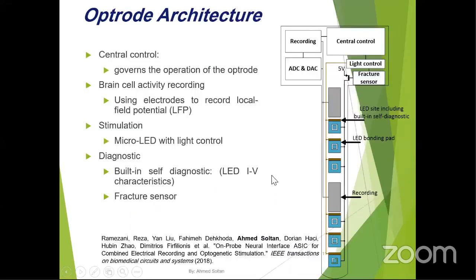Okay, and again, a block diagram of the Optrode architecture, which shows the control unit. It was a finite state machine unit to control when we can do recording, when we can do stimulation, and, whenever I'm doing recording, whether I can do stimulation, and how I can manage between recording and stimulation. It's a kind of internal control system, a very simple finite state machine to control the response of the system. And this is the first part of the system, the control unit. This control unit basically communicates with the control system, which is responsible for the algorithm, and sends the commands to the control unit in order to do stimulation or recording, or pause at the same time.